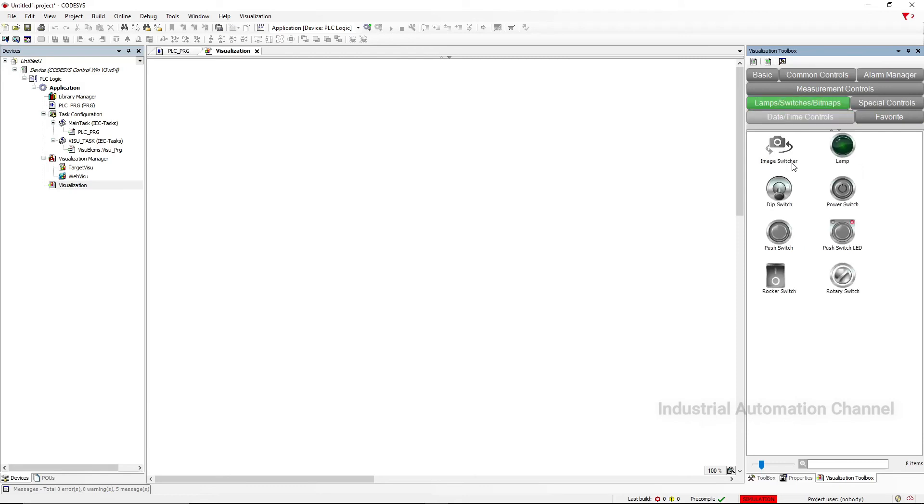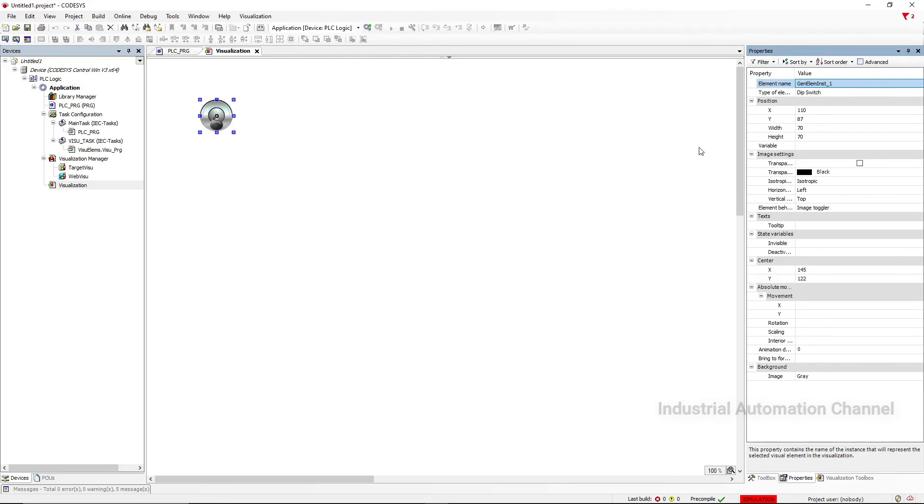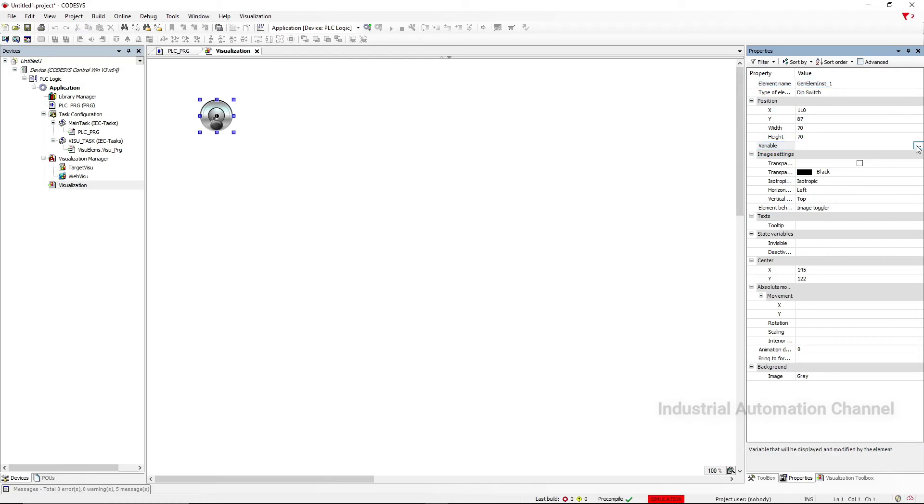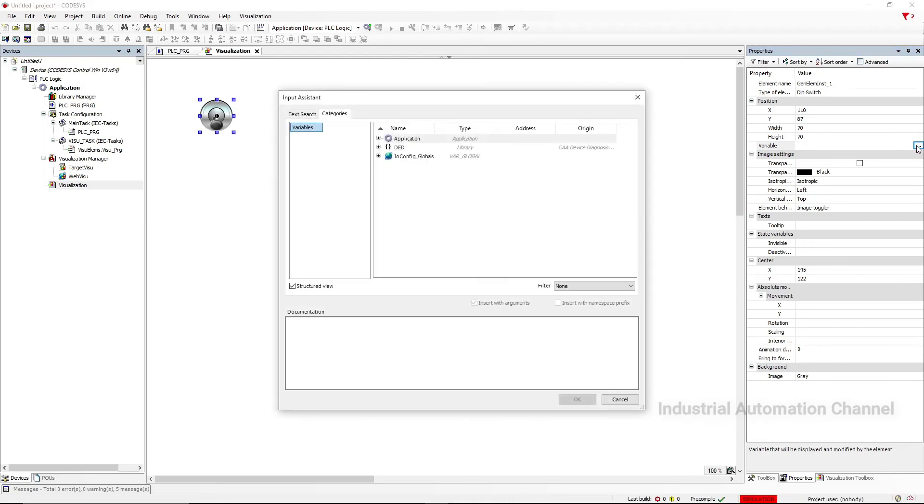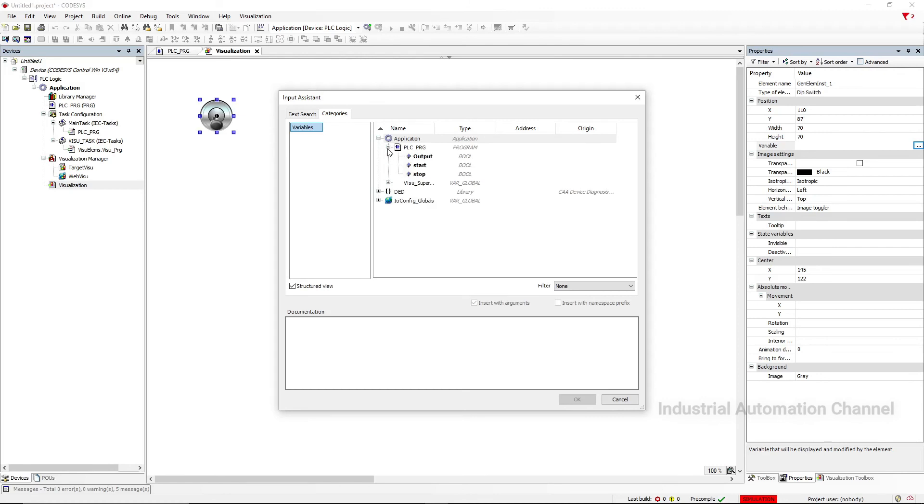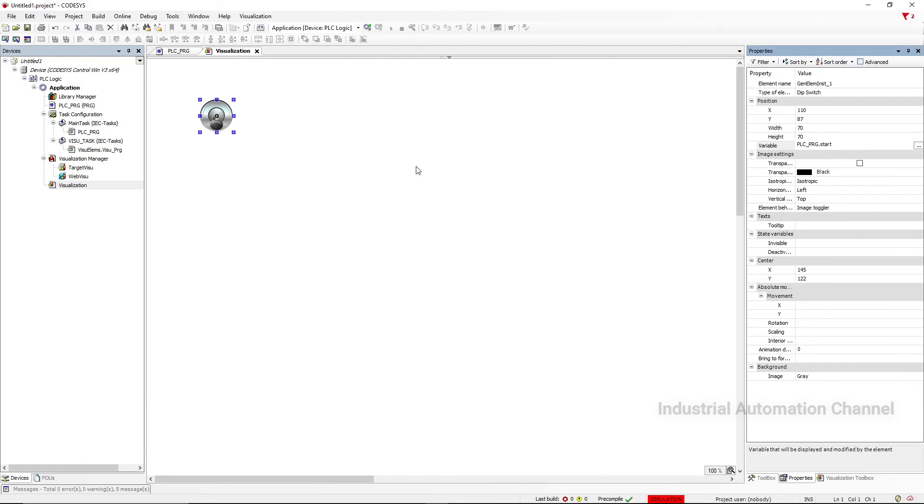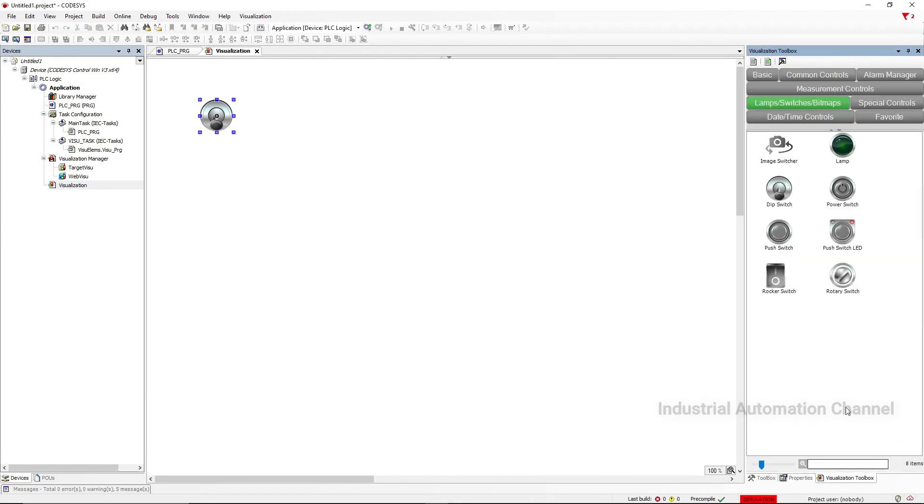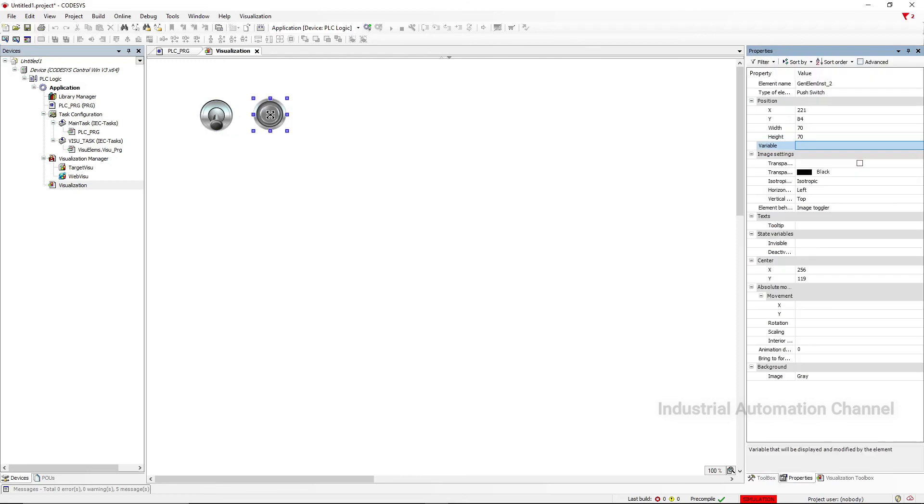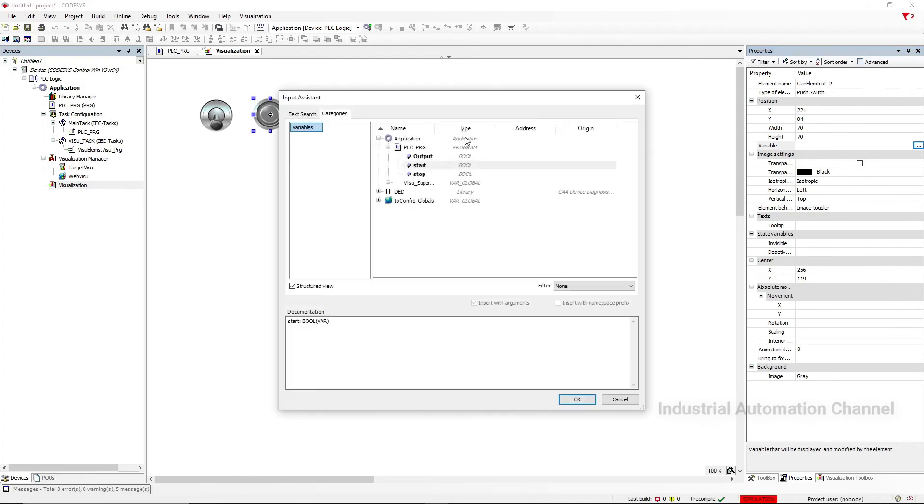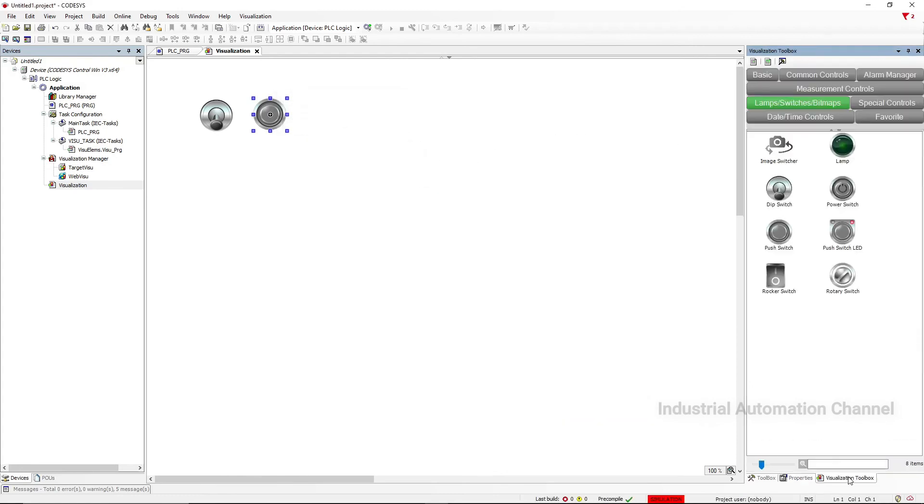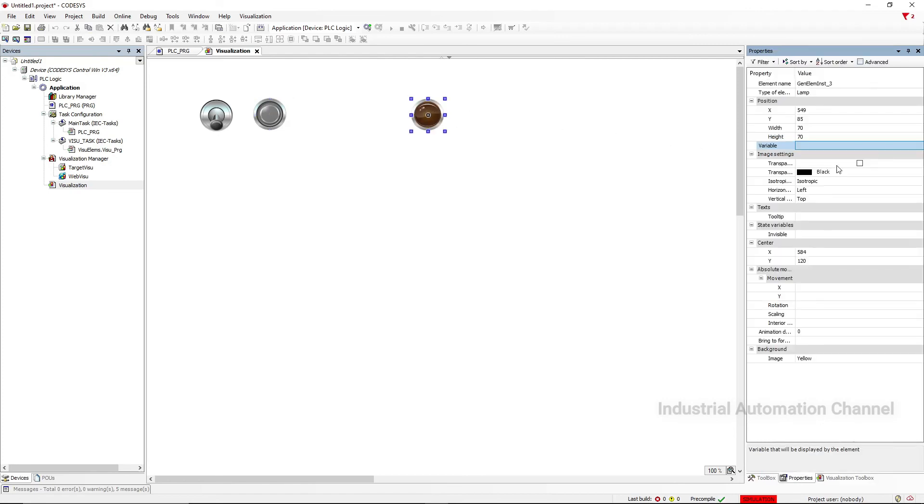Open visualization. In the right side click on Visualization Toolbox. You will see all the elements for visualization. I insert one switch for Start and Stop and a pilot lamp for output. As a variable of the switch, double-click here then click on the little box here. You need to determine the variable by clicking on Application, PLC Program, and Start variable. Insert the Stop button. Then go to the Toolbox and select Pilot Lamp. Again for the variable, assign the Output.